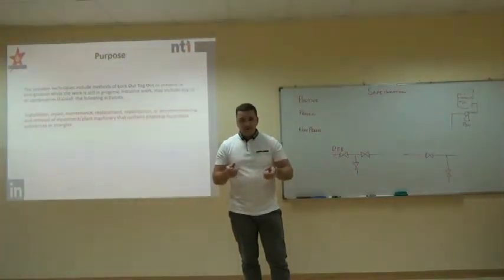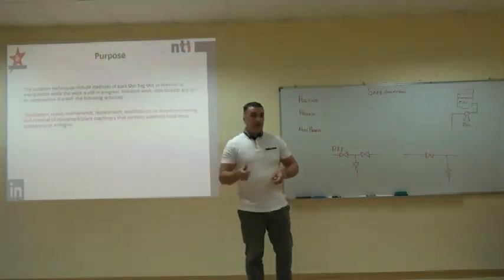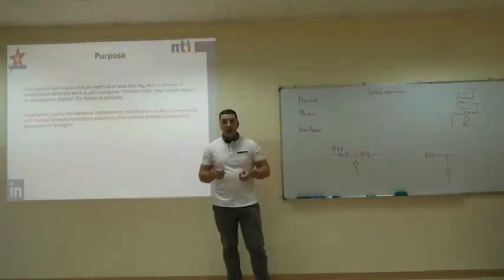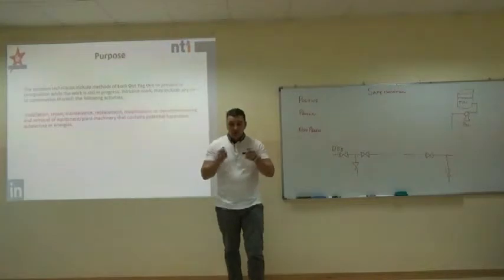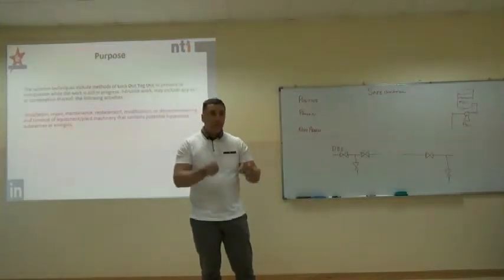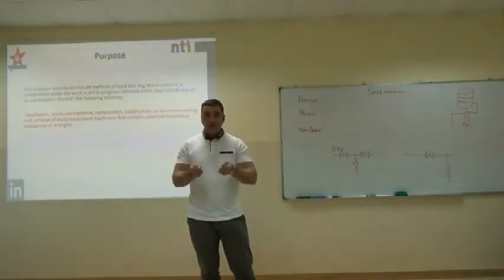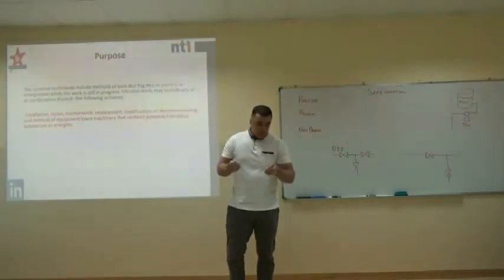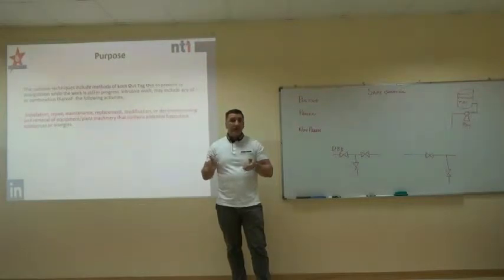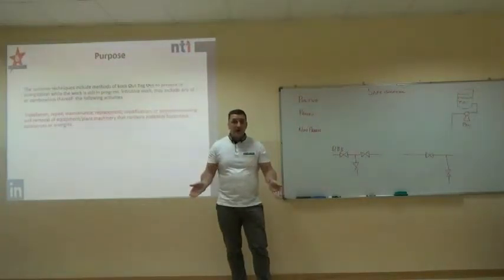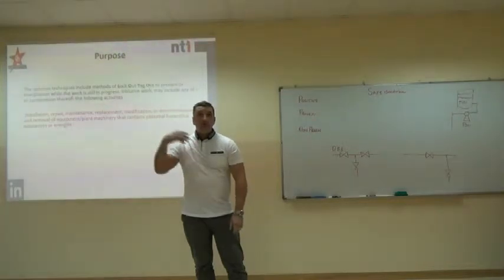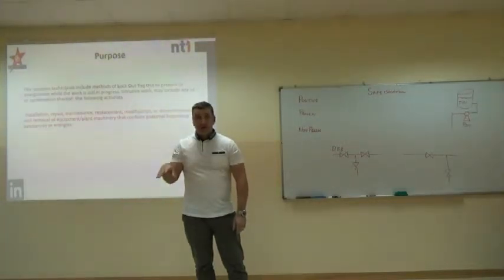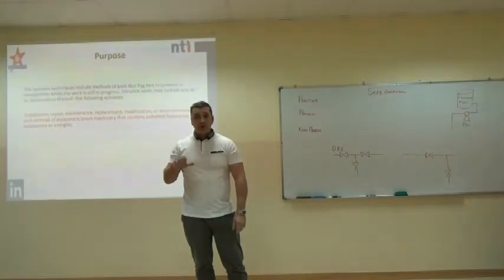The danger is, when we do a task every day and repeat it, if we do the same task every week we become complacent. Best practice is we should take the latest P&ID, go out to the equipment, walk the line, and make sure the P&ID reflects plant conditions. The process industry is 24 hours. We could come back from two weeks' vacation and find contractors have installed another line. We should always go out, identify the hazards before we do anything or write any document for the task.